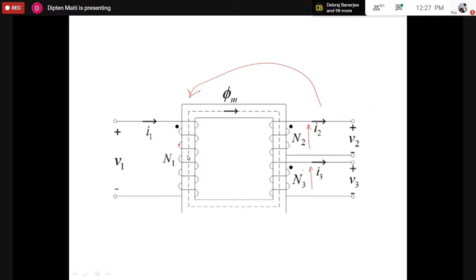Without opening the transformer, it's not possible to know whether the coils are wound in the same fashion or manner: all clockwise, one clockwise and one anti-clockwise, or two clockwise and one anti-clockwise, this way. However, there is a method by which we can do this without opening the transformer. In fact, this is very important when we want to connect two transformers or two coils in parallel or series. We would go into that a bit later, just after this, using the polarity test.